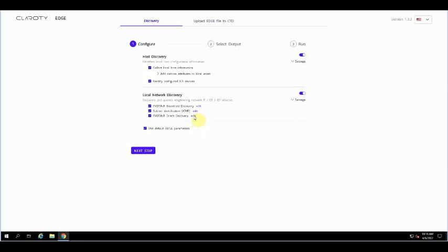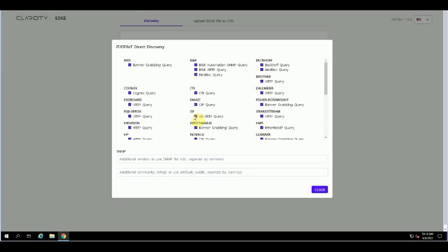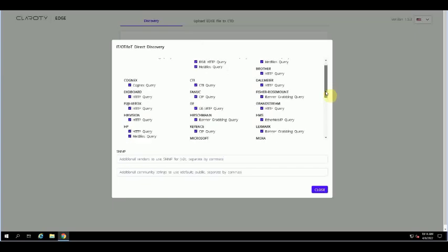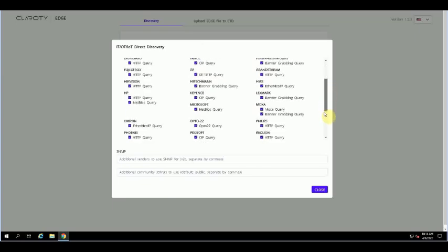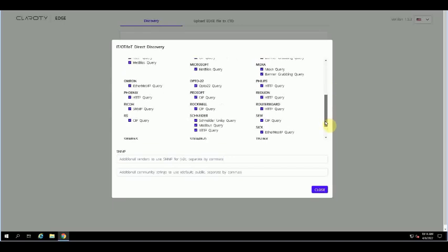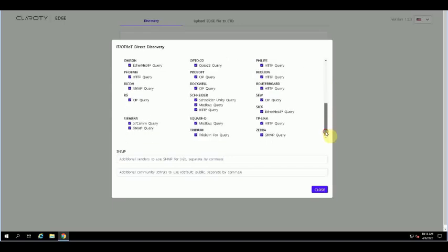Direct discovery is a bit more comprehensive. Based on what devices were discovered during the broadcast discovery, CTD will initiate a device-specific query for each device type that was discovered. So we could say that the discovery has two phases. Broadcast discovery asks what device types are out there, and direct discovery counts the number of devices of each type.